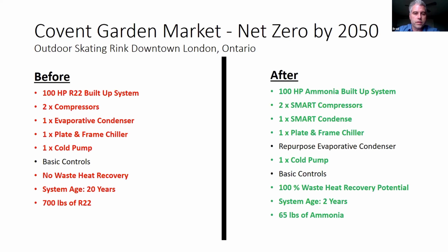They repurposed their condenser as a cooling tower and left the controls in place, but now they can tap into that waste heat. The other key thing to note is they were able to lower their charge 90%, going from 700 pounds down to 65 pounds of ammonia, and the efficiencies are still the same, if not better.